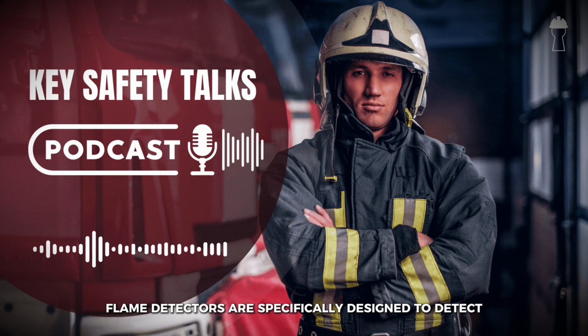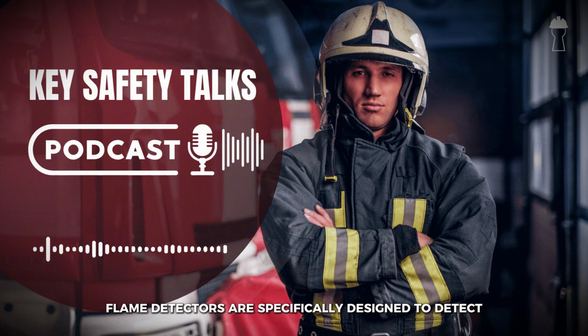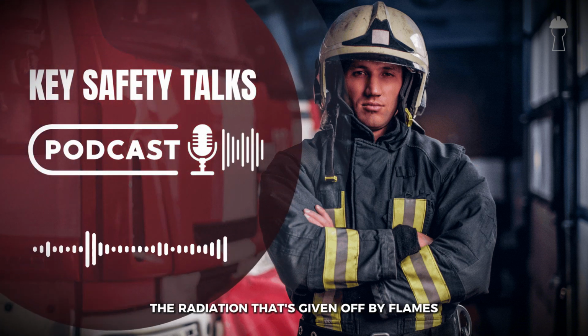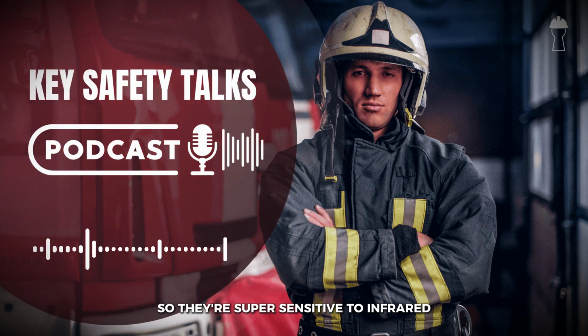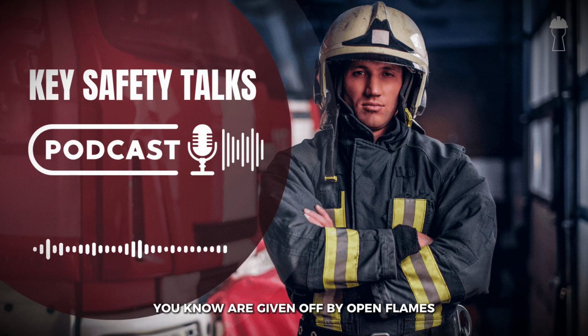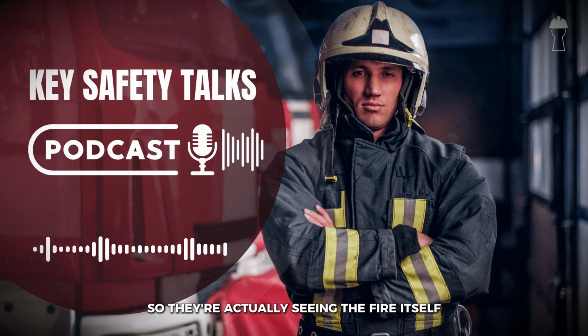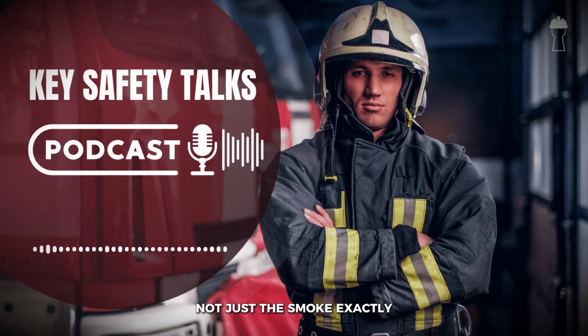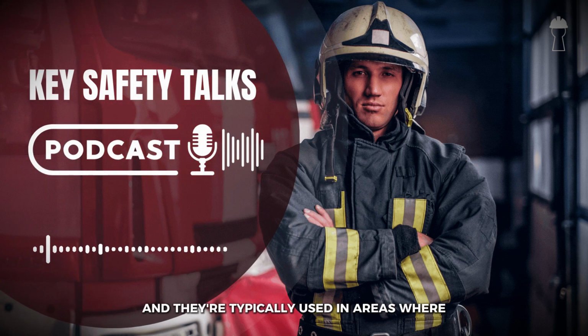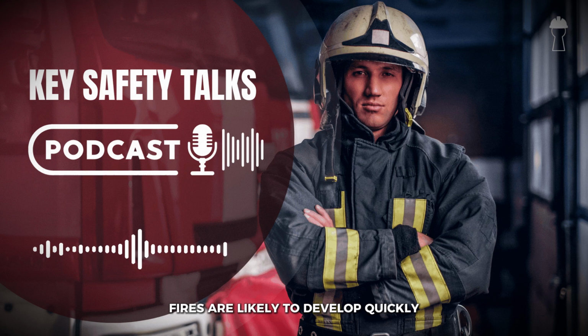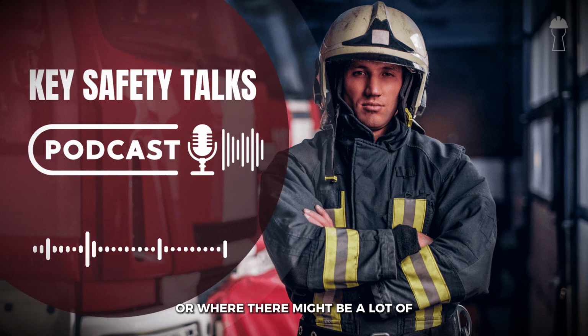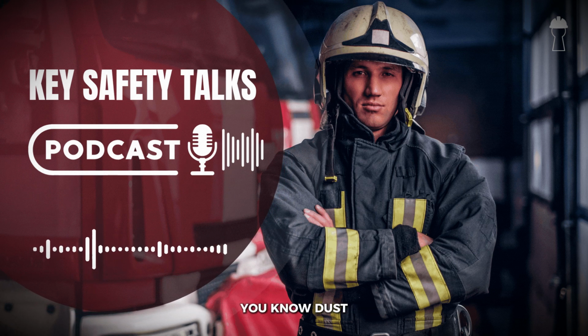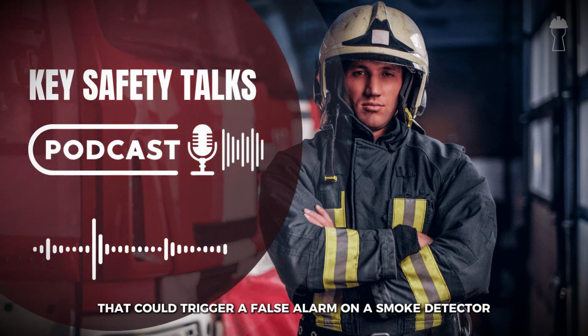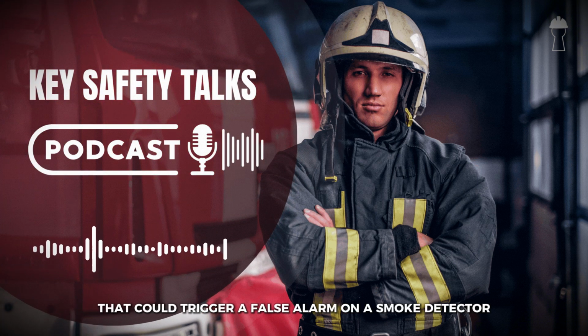How do those work? Flame detectors are specifically designed to detect the radiation that's given off by flames. So they're super sensitive to infrared or ultraviolet light, which are given off by open flames. So they're actually seeing the fire itself, not just the smoke. Exactly. And they're typically used in areas where fires are likely to develop quickly or where there might be a lot of dust or other particles that could trigger a false alarm on a smoke detector.